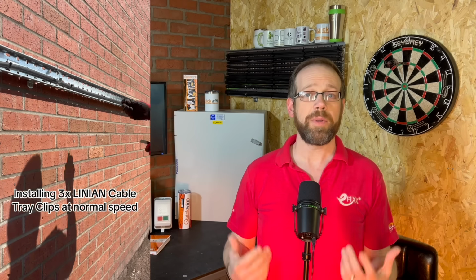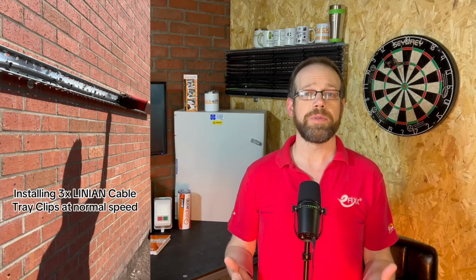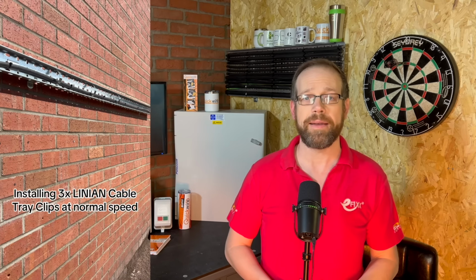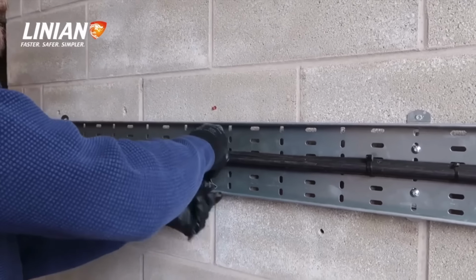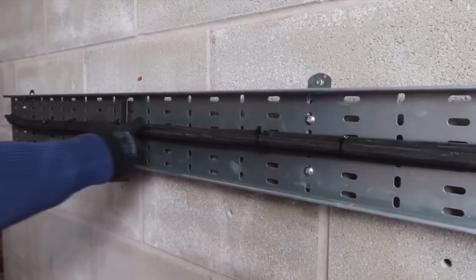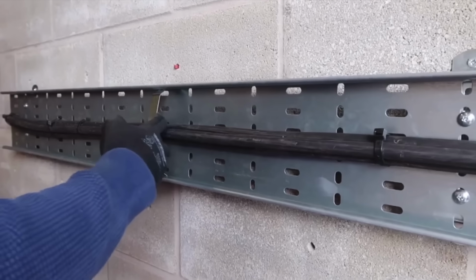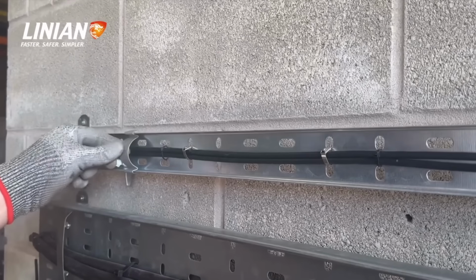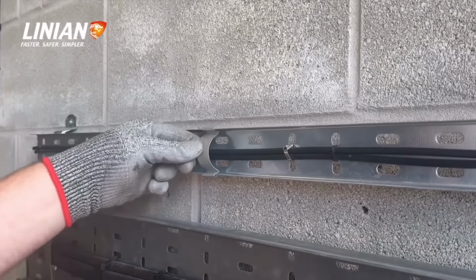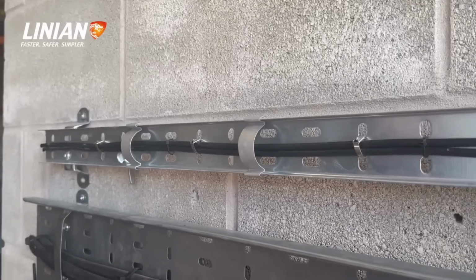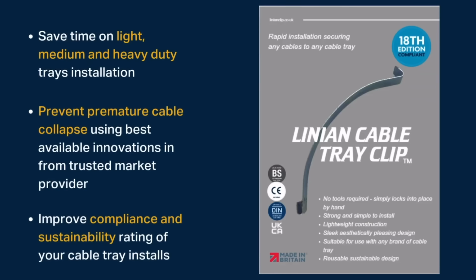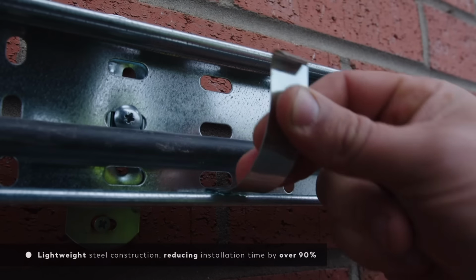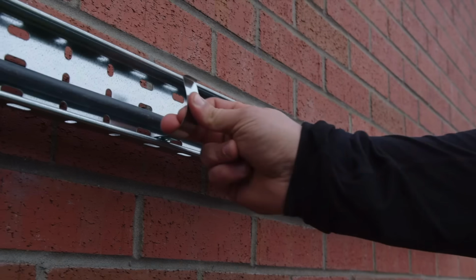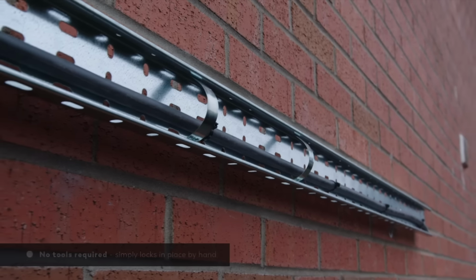Linian has unveiled a special clip for cable trays. It can be used with any brand of tray and doesn't need any tensioning tools or steel cable ties. You simply lock it in by hand. Linian says its customers are reporting installation times that are 90% faster than other methods. The clips are BS 7671 compliant and come in 5 sizes ranging from 50mm for light-duty cable trays to 225mm for medium and heavy trays. The pull-out force ranges from 20kg to 200kg depending on size. The clips are made in the UK with fire-rated steel. They're also non-corrosive and weather resistant. All of this makes them perfect for preventing the premature collapse of cables in the event of a fire.